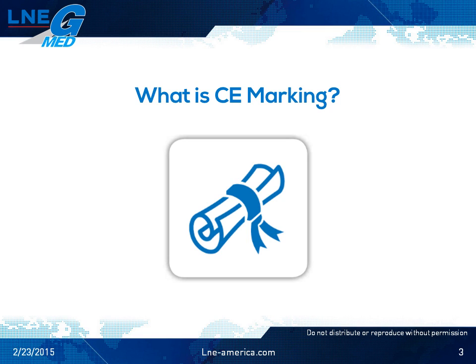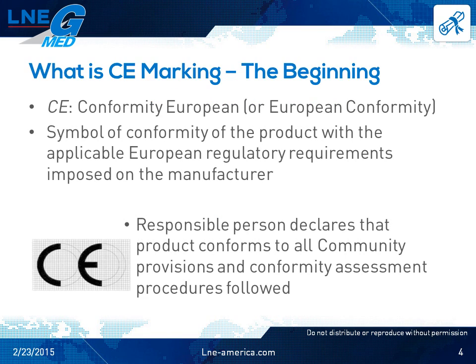First, let's go through what is CE marking. The CE in CE marking stands for Conformité Européenne, or European Conformity, if you are an Anglophone. When the CE is affixed to a product, be it a medical device or something else, it means that the person responsible for manufacturing the product, according to the directives, declares that the product conforms to the applicable European Community provisions and that they followed all the necessary conformity assessment procedures.